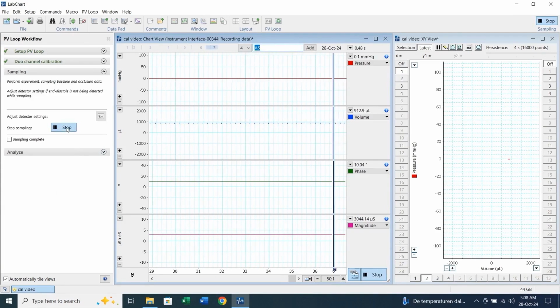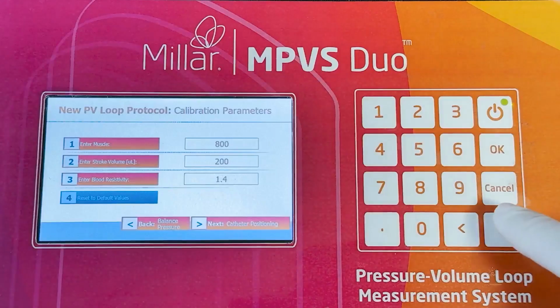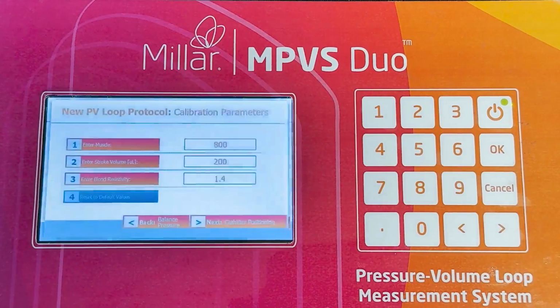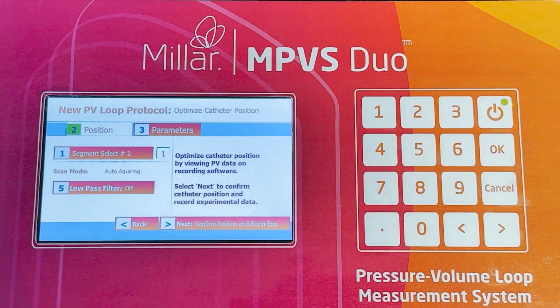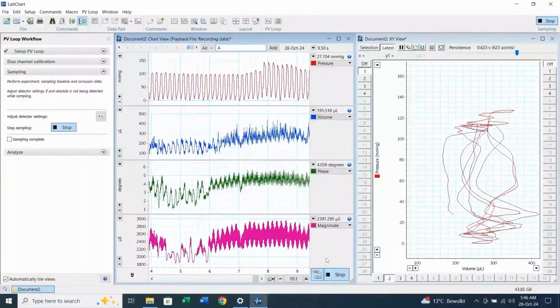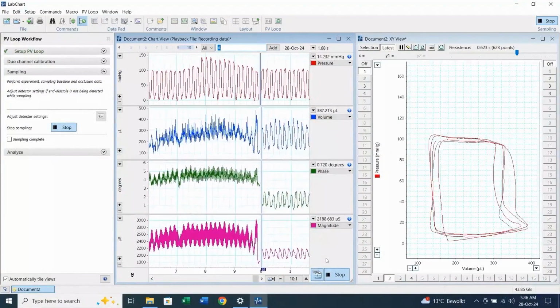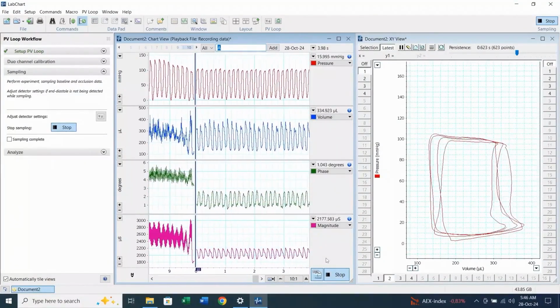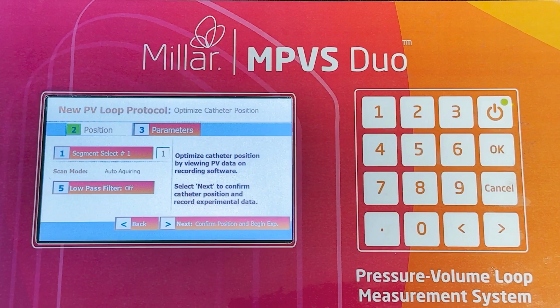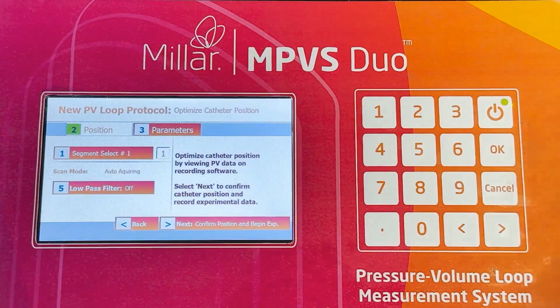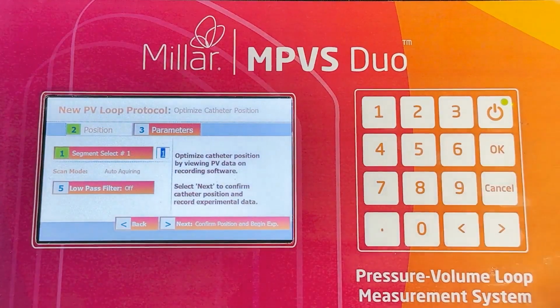Click on Start Sampling. On the Duo, press the forward arrow to move to the Optimize Catheter Position screen. Introduce the catheter into the ventricle. For small animal catheters, only one segment selection is available. For large animal catheters, make sure you select the segment with the size suitable for the animal's ventricle. To do this, press 1, and then the segment number and OK to select. Please see the manual for more information on the segments.